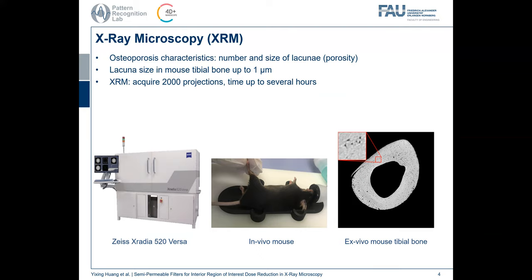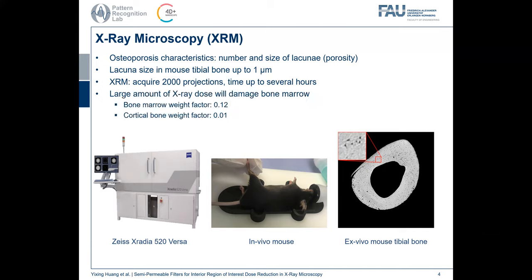However, it has to acquire more than 2,000 projections and the acquisition time is up to several hours — for example, more than six hours. Therefore, the large amount of X-ray dose will damage bone marrow because the bone marrow is very sensitive to X-ray dose. Its weighting factor is about 12 times that for cortical bone tissue.